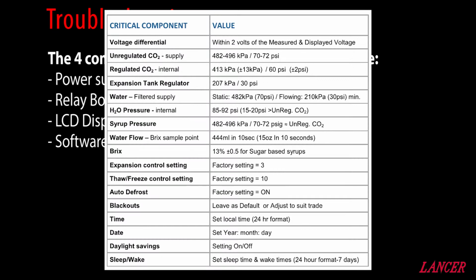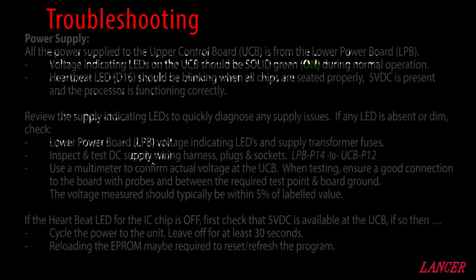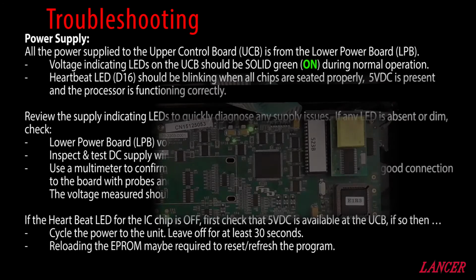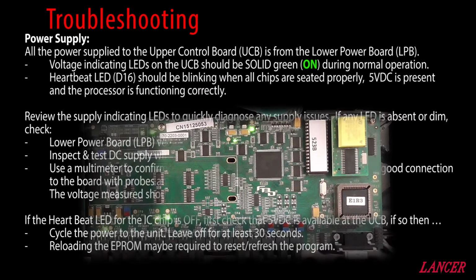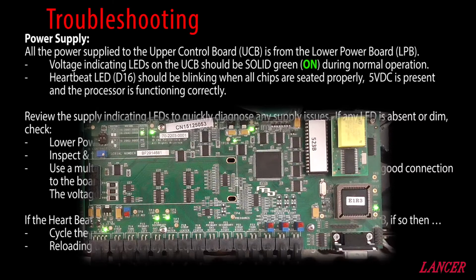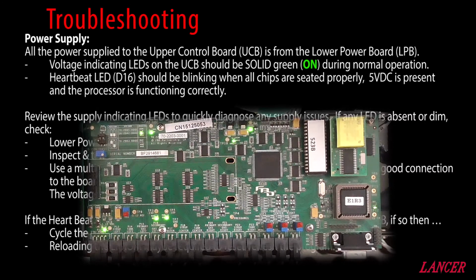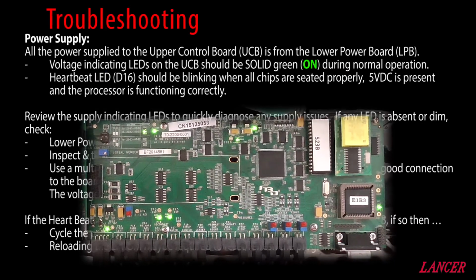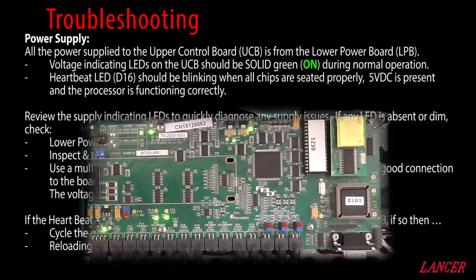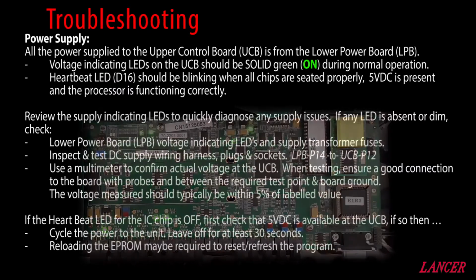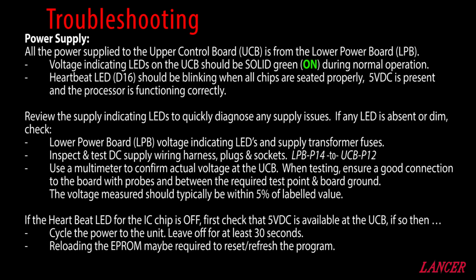Start by checking that the unit is set up correctly, the critical settings, reviewing supply voltages, pressures, flow rates, and then make sure the program's running okay. All the power supplied to the upper control board originates from the lower power board. The voltage indicating LEDs on the upper control board should be all on during normal operation, and the heartbeat LED should be blinking when all the chips are seated correctly and the 5V DC is present and the processor is functioning correctly. Review the supply indicating LEDs to diagnose any supply issues.